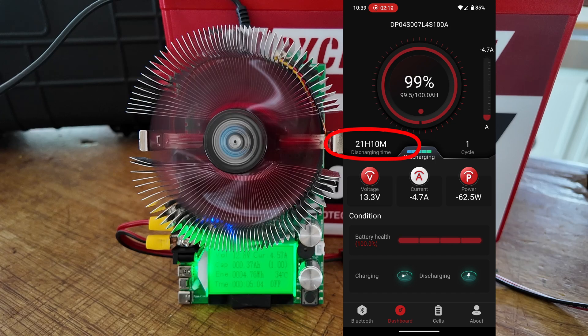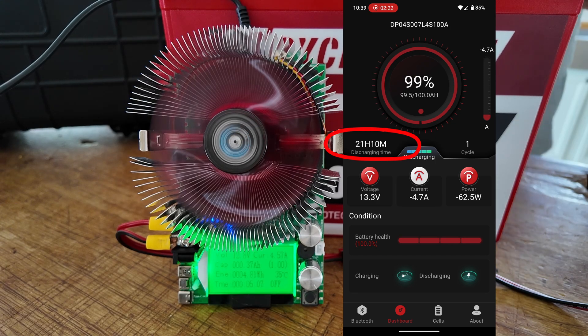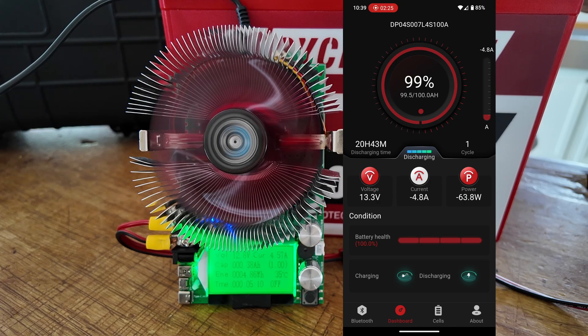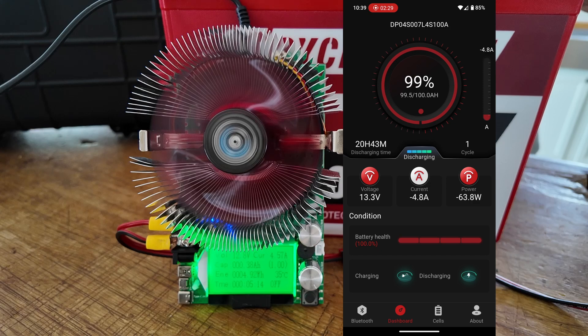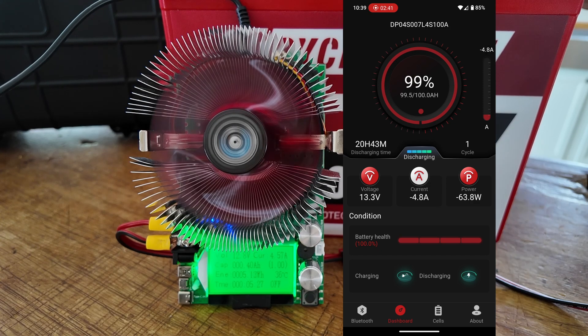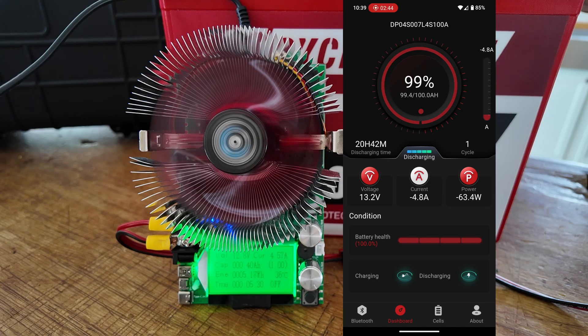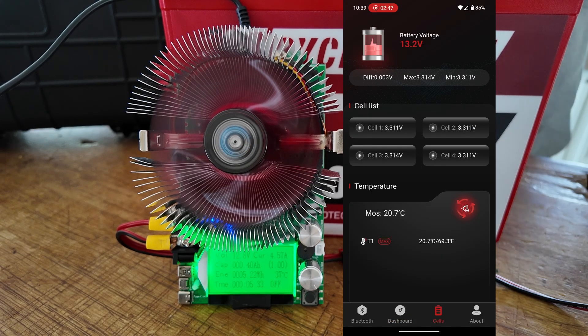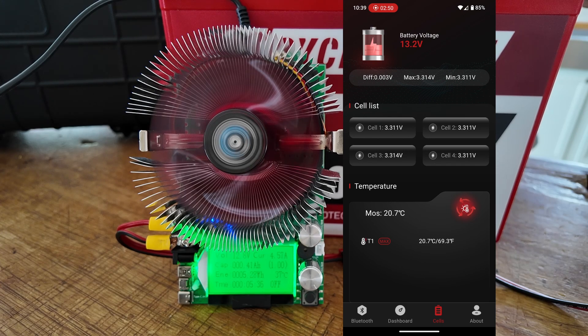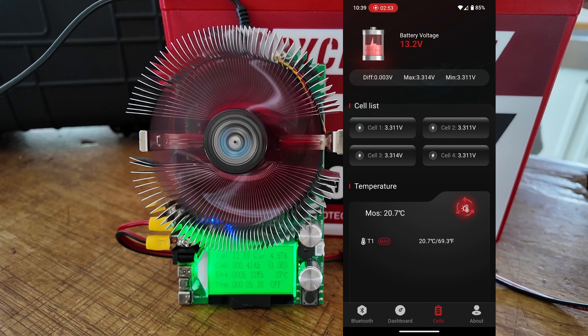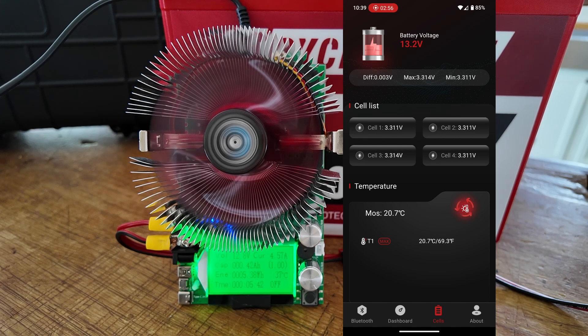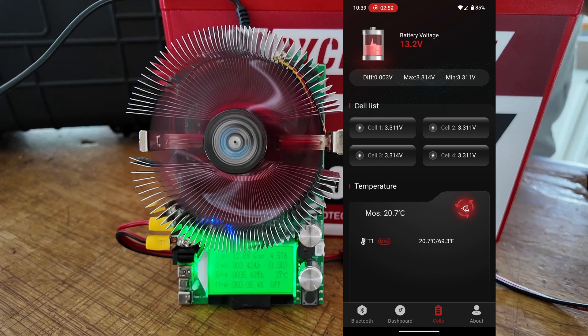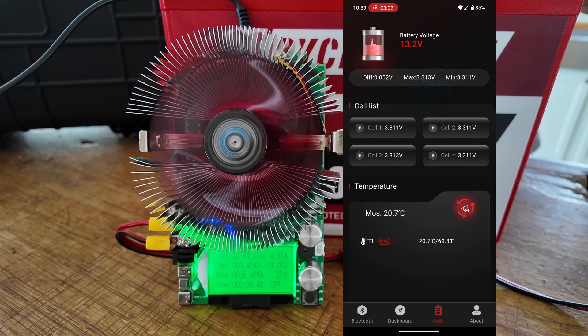Also notice that it gives us the discharge time, and that's the amount of time that it will take to discharge the battery entirely, given the current rate at which we're pulling power out of this particular battery. If we click on cells down there at the very bottom, it will bring up a list of our cells and give us the individual cell voltages. And you can see that they are all very close to 3.31 volts. There is some slight differences, but that's to be expected, even when these batteries have been fully balanced.